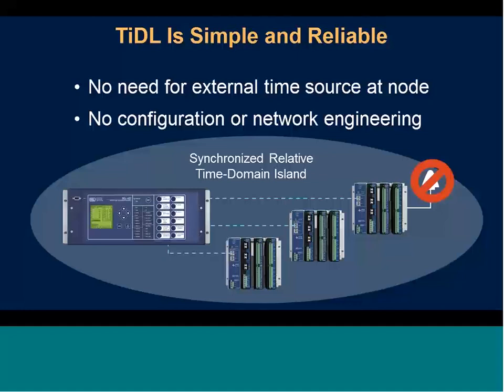With that being said, the relay does still have a time signal on it, so you can still connect it to time, and that's generally best practice for wide area analysis—you want a time signal to your relay. But if you were to lose your time signal, your protection can still remain up and running regardless of that signal being present.